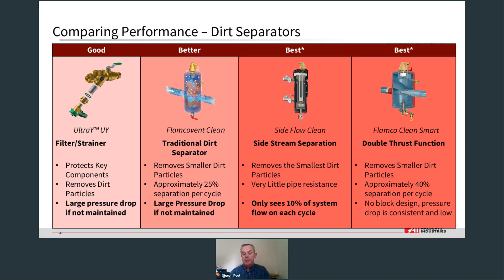This way, many of the micro bubbles and dirt particles are propelled to separate plenum chambers, which help produce an exceptional level of dirt and air separation. So, similar to side stream filtration, we take 10% system flow to achieve 40% air and dirt removal on each cycle. Then there's side stream filtration, again a partial flow method through a filter or strainer. Another advantage is there's very little resistance in the system, but it may take a little longer to clean the system than an inline unit.